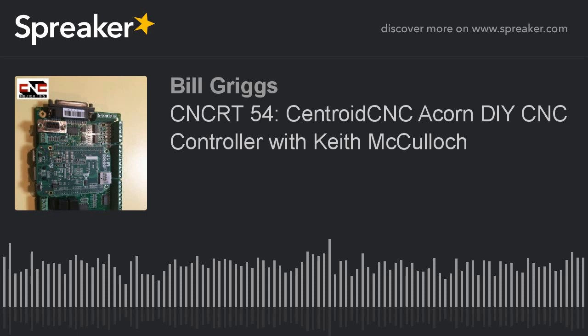Okay. And then you have another wire, if you want to. Most guys end up doing this. It's not required. Another wire that runs back from the VFD into one of our inputs, and that's the fault signal. So that if that VFD ever stalled for some reason, we would know it, okay? And we wouldn't just keep on going. We would issue an e-stop condition at that point and all stop if the VFD told us, hey, something's up.